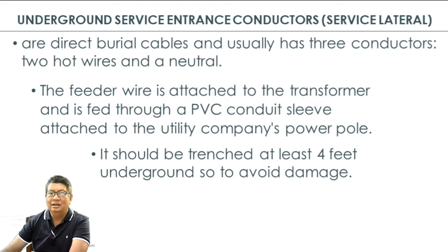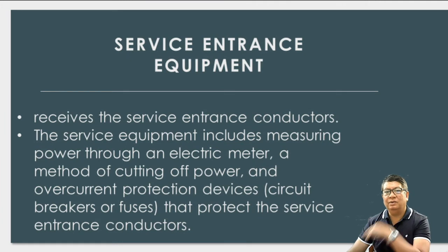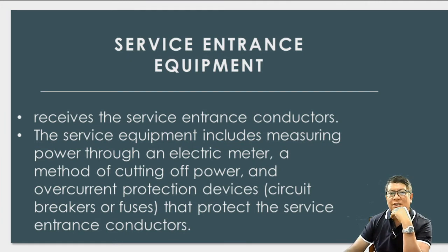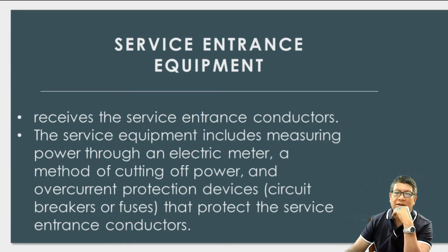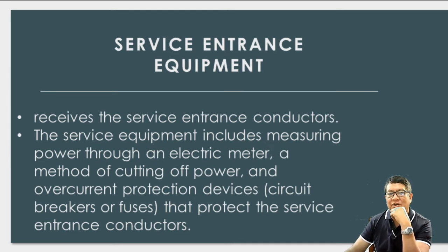We have the service entrance equipment, which receives the service entrance conductors from the weather head. The service equipment includes measuring power through an electric meter, a method of cutting off power through the main disconnecting means, and overcurrent protection devices like breakers and fuses that protect the service entrance conductors. So we have these protections in our service entrance line.